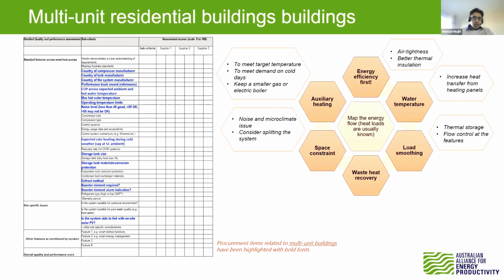The space constraint, you spoke about that brilliantly. You provided an example of that. What we mean by that is the required floor area. We have talked about that in the guidance document, and also the noise that needs to be controlled, and of course the microclimate effect that you explained there. With microclimate effect, what we are referring to is being able to avoid temperature drop around the heat pump system just because of its own operation.